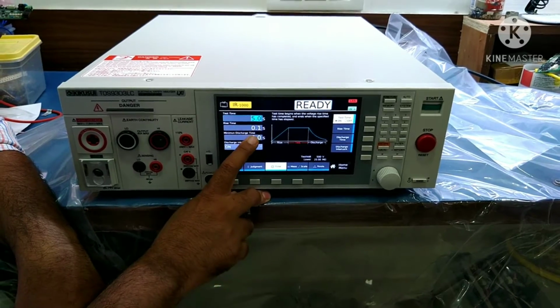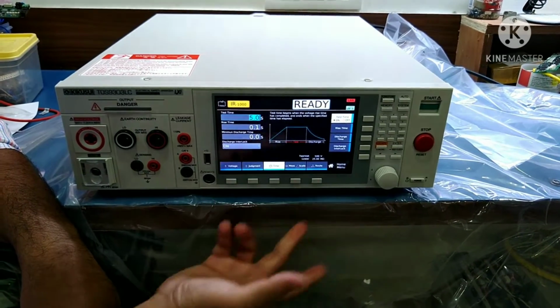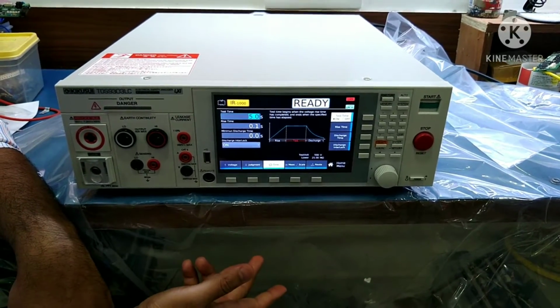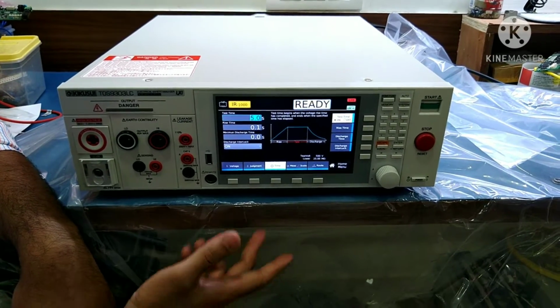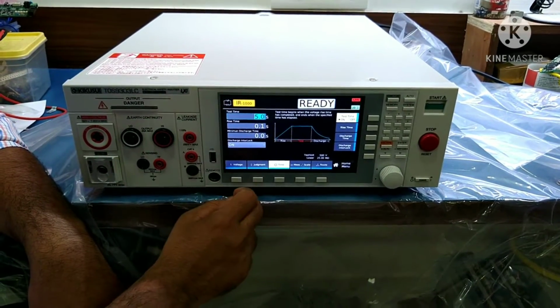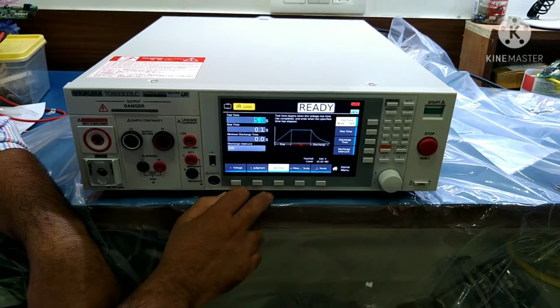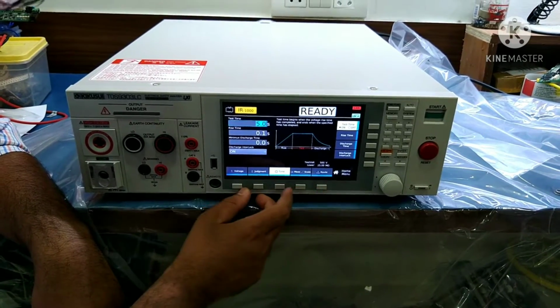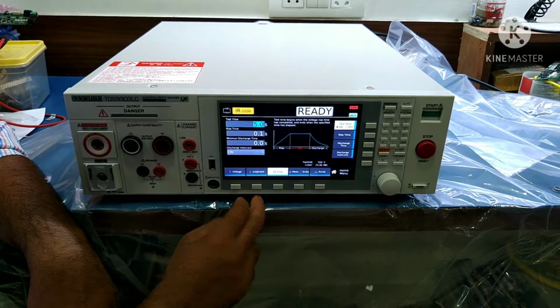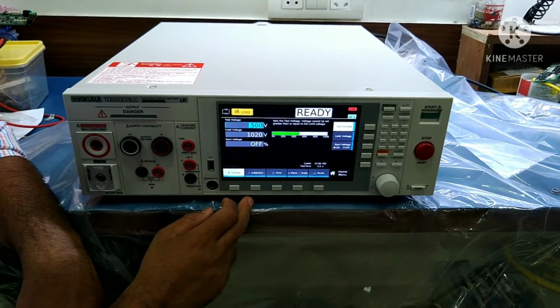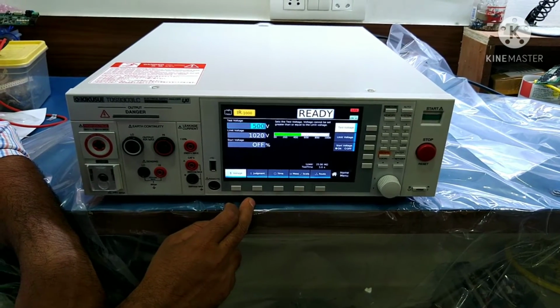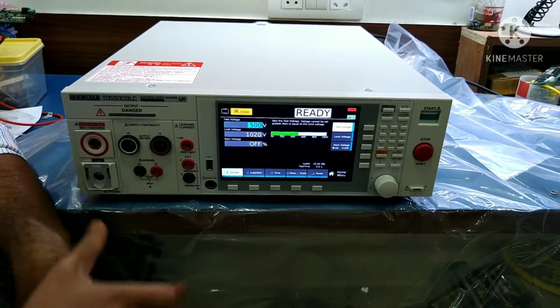The 5 seconds rise time is the default. If you want to increase it, you can set 1 second per voltage from here. So right now I am keeping the default settings. This is the basic setting of the IR section. Now I'm going to start the voltage.